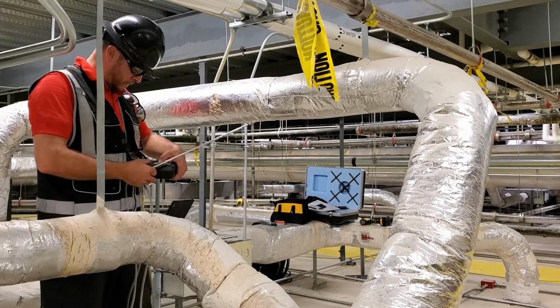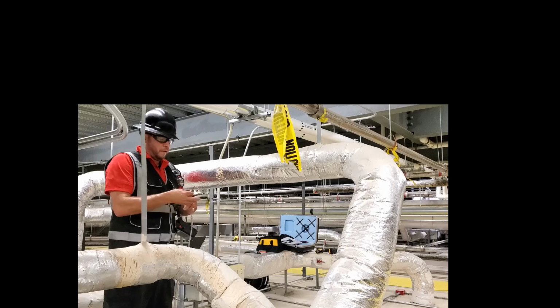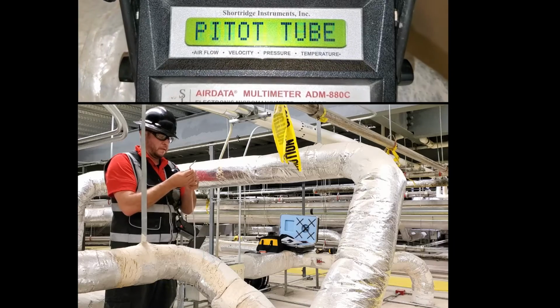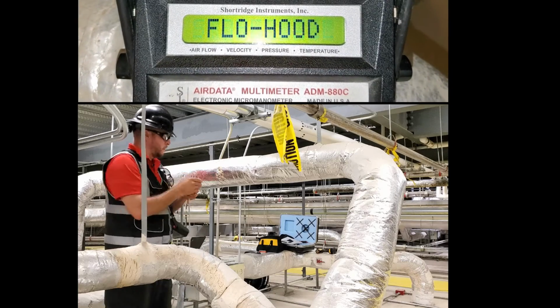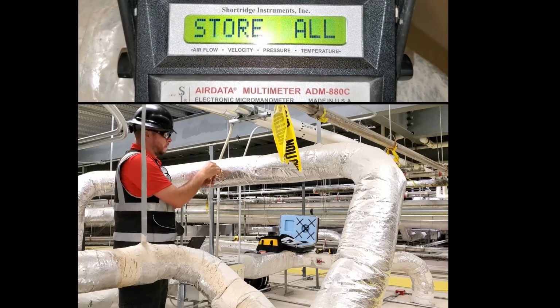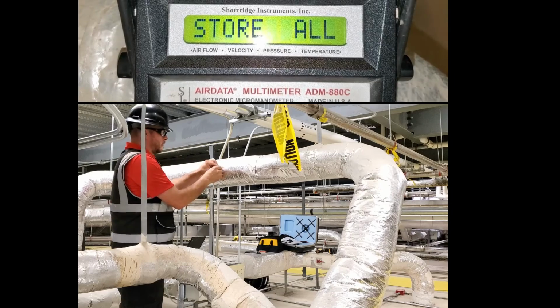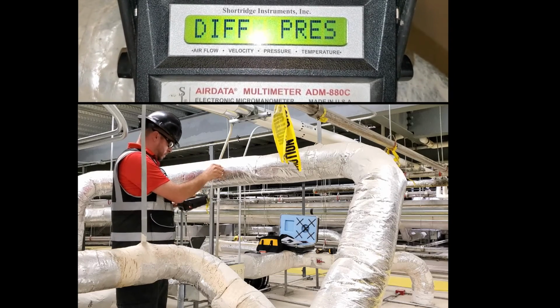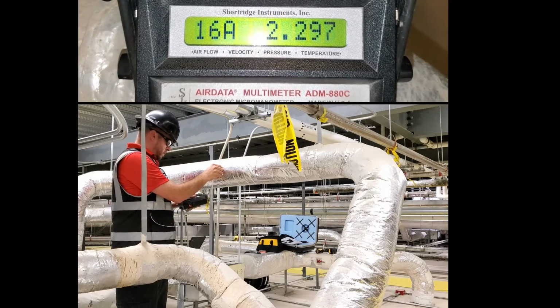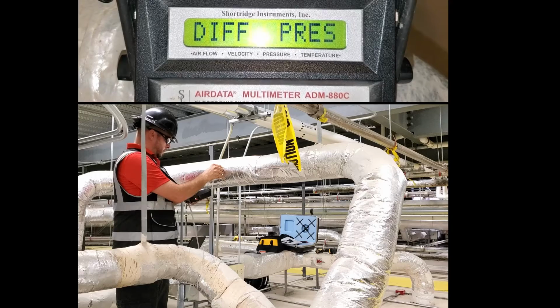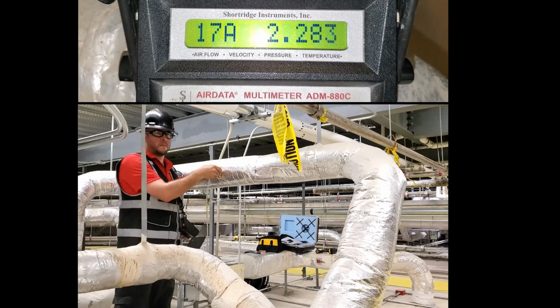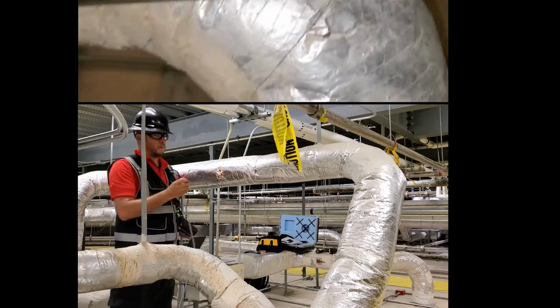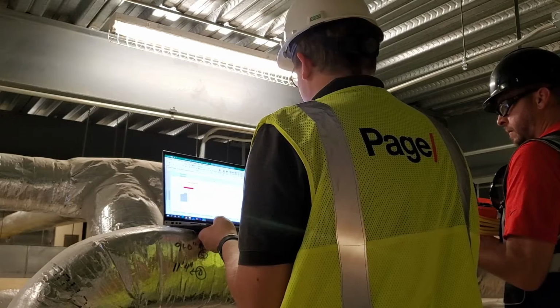It's just, unfortunately, in this situation, since we're upstream of the terminal unit, we can't really utilize the static to calculate a CFM. So generally, a way around that is you can utilize velocities on certain reading points, and it can help you get close, but still you want to follow it up with a traverse.